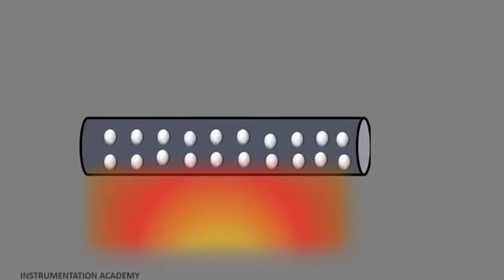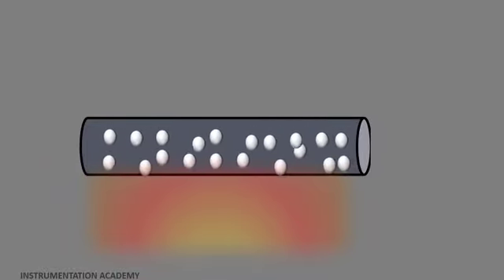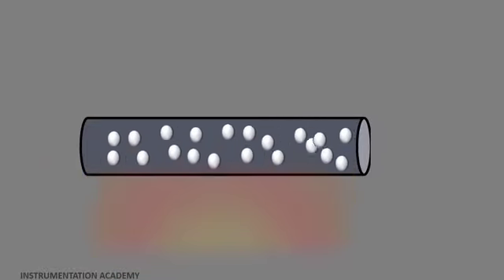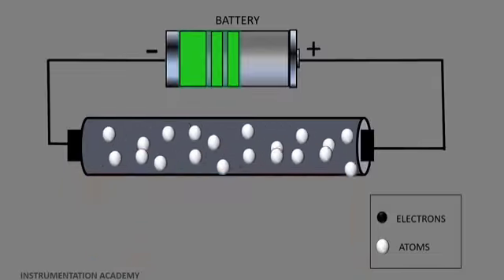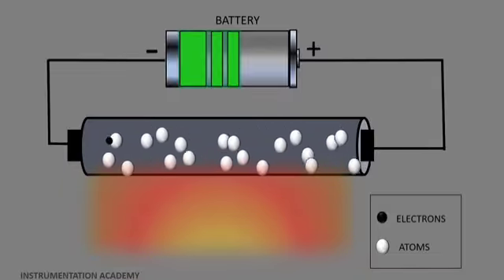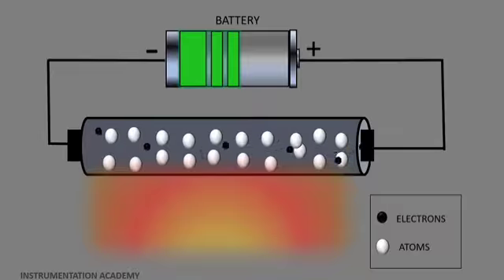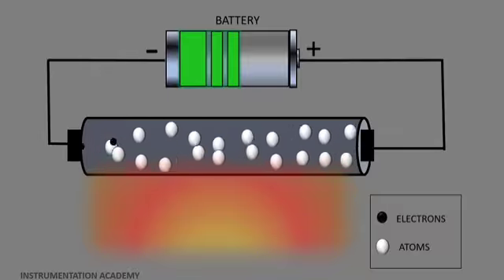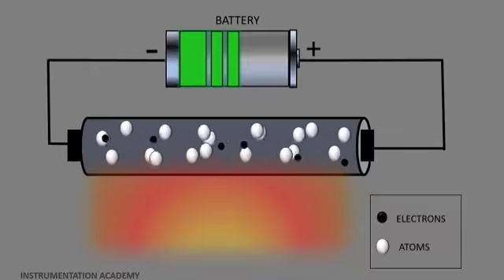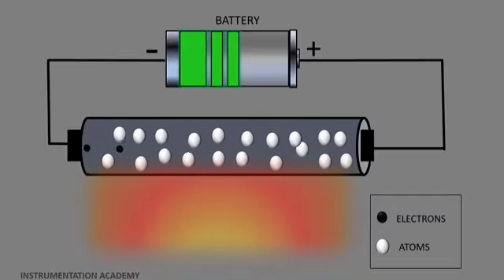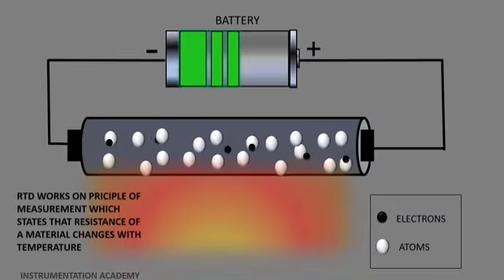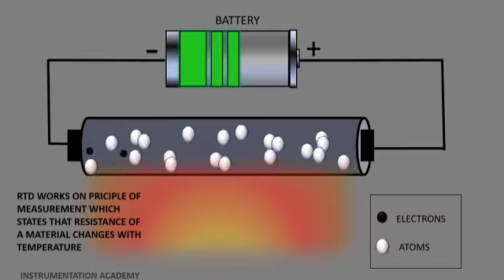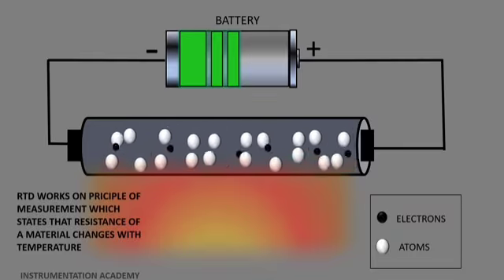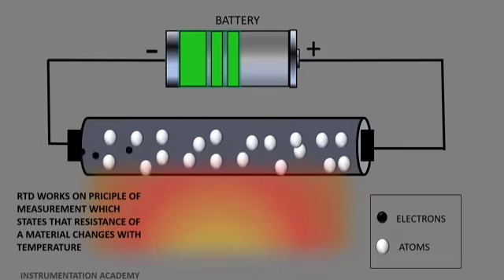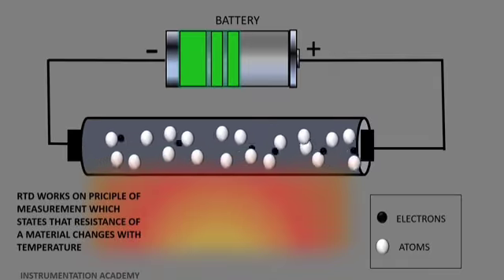Now, when we heat the conductor, the atoms of the conductor absorb heat energy. As a result, their vibration increases. Because of this increase in vibration, the collision of electrons with atoms also increases. And so it becomes very difficult for electrons to move across the conductor, and hence the resulting output current decreases. An RTD works on this principle of measurement, which states that the resistance of a material changes with temperature. As the temperature of the metal increases, the metal's resistance to the flow of electricity also increases.